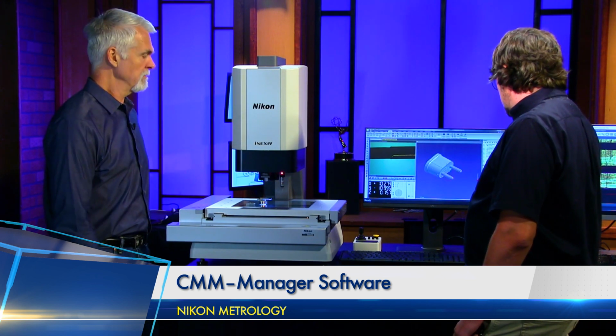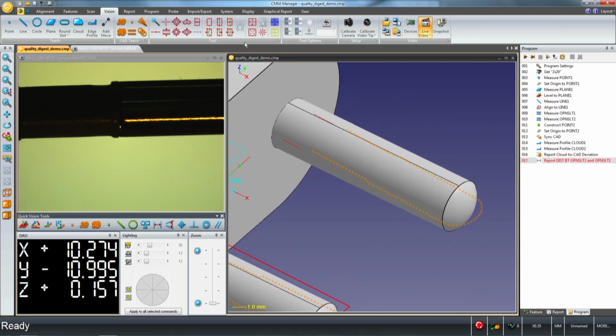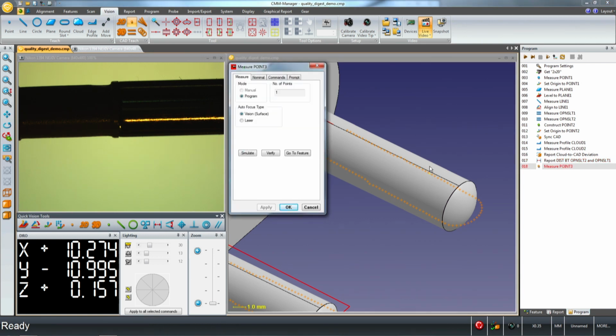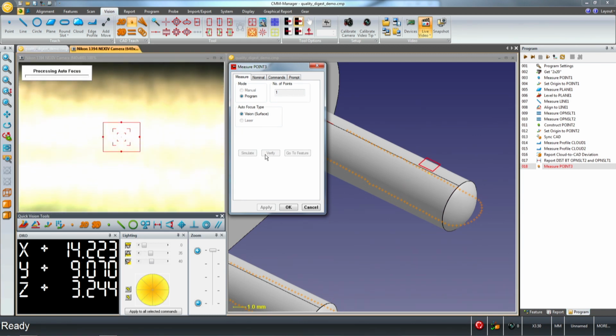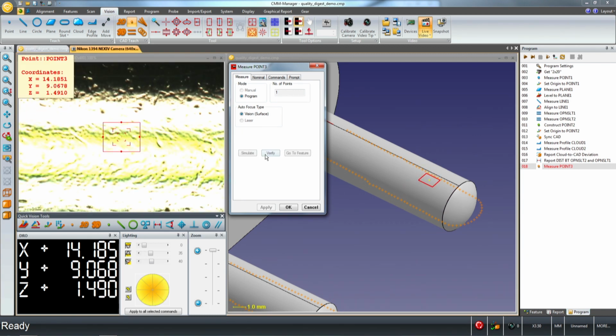Yeah, that's right. Okay. So if I come here, for example, and tell the software with a vision tool that I want to measure a point maybe on the top of this cylindrical feature, immediately the software, because I'm using autofocus, knows to change to a high magnification and performs the measurement. There it finds where that particular surface is in focus and gives us a Z value for the depth of that point. Okay.